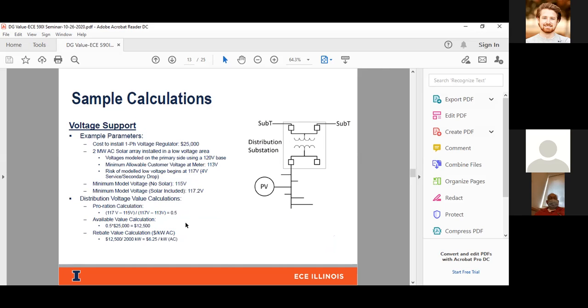Similar to the capacity value, this is a quick example for voltage value. Same thing: the cost to install a single phase voltage regulator is about $20,000. We install a 2 megawatt AC solar array in the area of the low voltage violation here. We would model the circuit with a 120 volt base, and you look at what the voltage is before and after adding the DG.